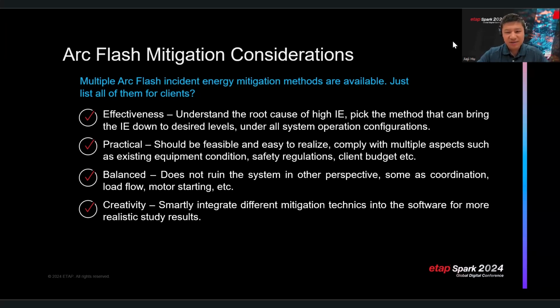It should comply with different aspects, such as the existing equipment condition, the client safety regulation, or even the client budget. For example, installing a differential relay on a bus can probably bring down your high IE to a very low level. But differential relay has more consideration, like CT wiring, your distance from the CT to your relay, even nuisance tripping. So differential relay may not always be the best option to recommend.